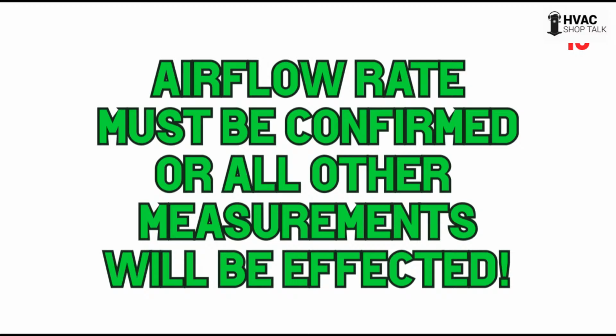Confirming airflow is just the first step of charging, capacity calculation, analyzing what's wrong with the system. It's got to be done correctly. And a lot of times it's so far off what it should be, you can say, well, I'm going to go and fix this because we can't check the other stuff, and you're going to cause yourself a lot of misery later where there would be joy.